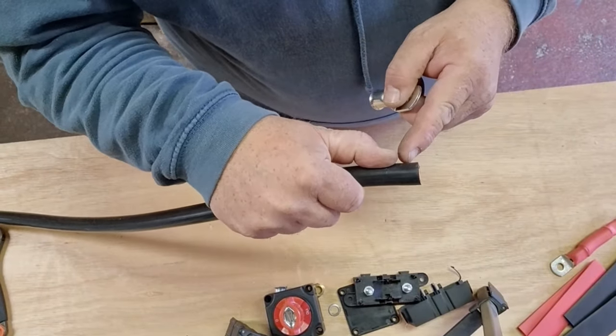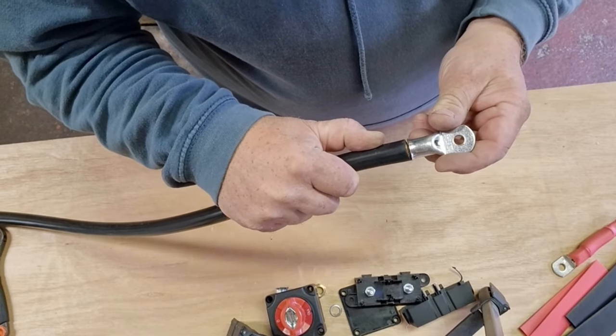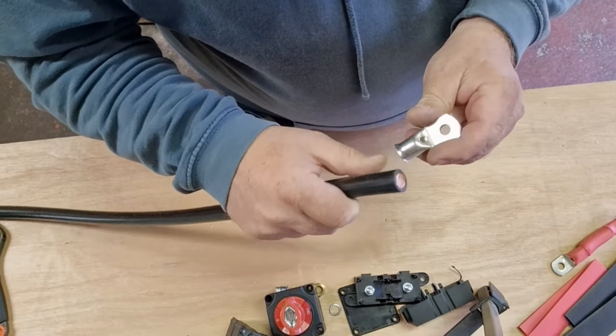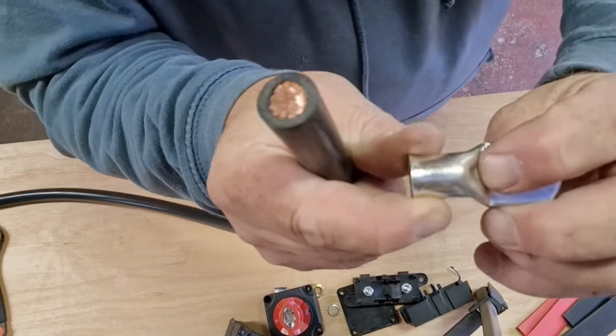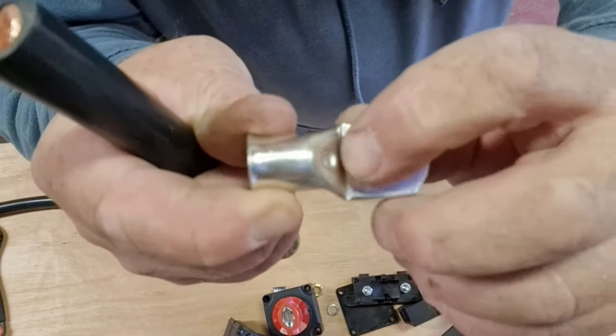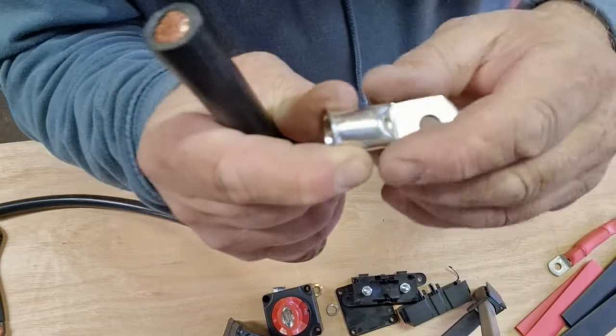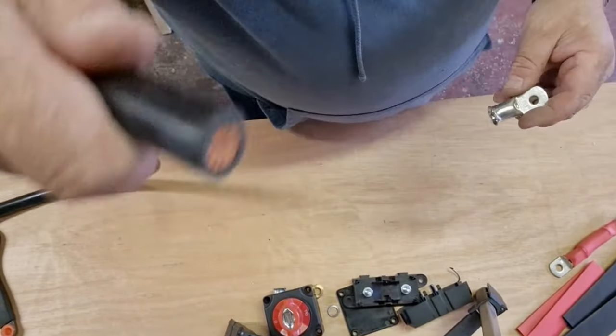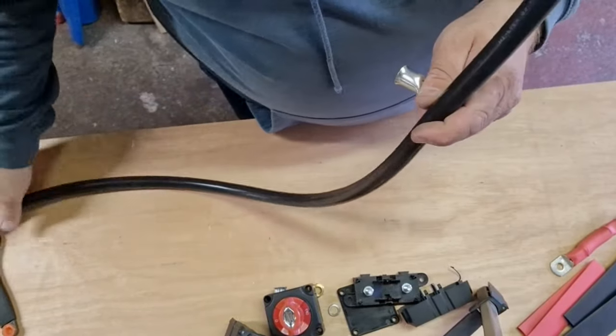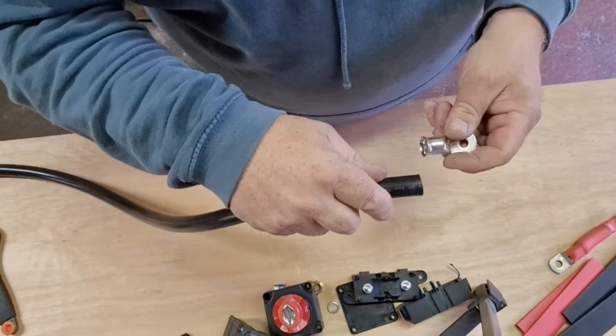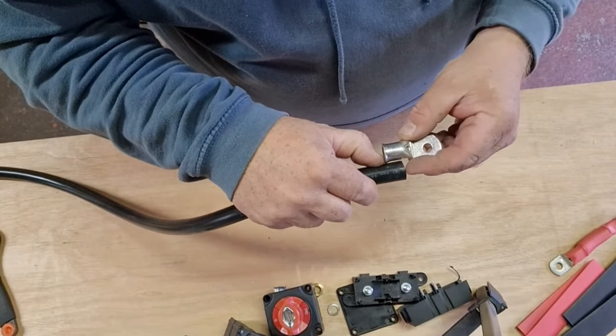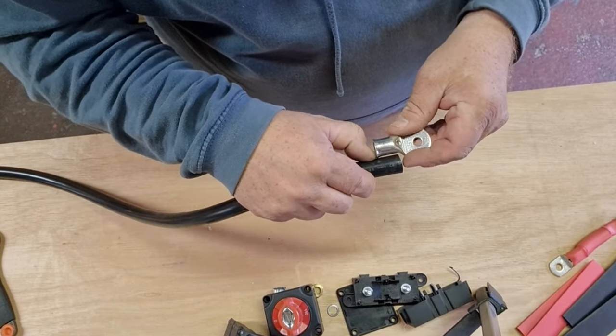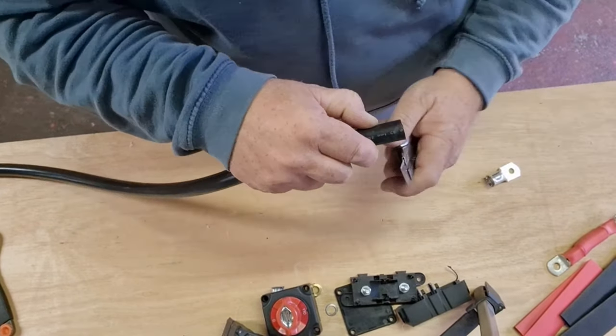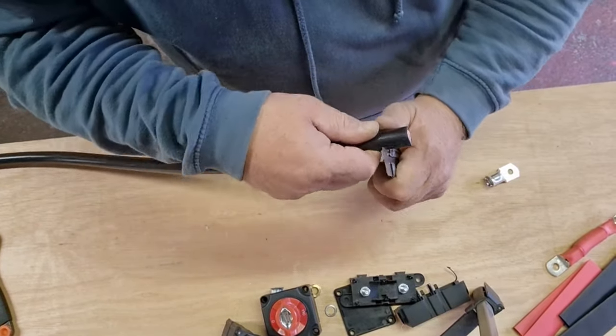So when we come to remove the outer sheath for the 95 to go on, the lug to go on, what we have inside there is a little lug, a little marker, and that's where we're going to measure up to. This cable's so flexible — what we're going to do is just trim off enough to push that right up. Don't take too much off, because that's the last thing you want to do.